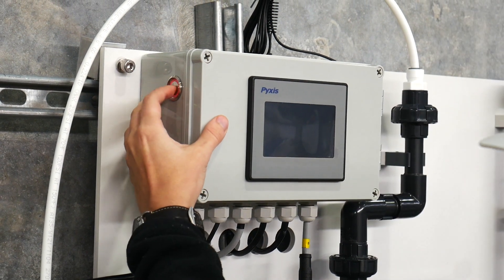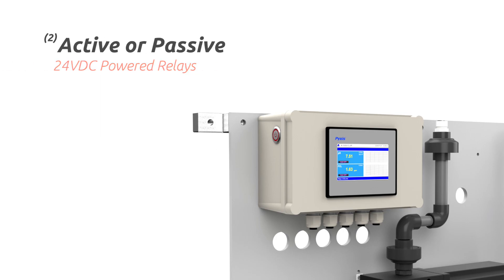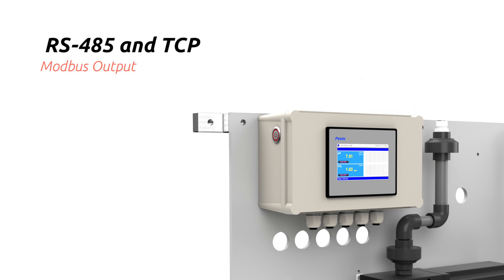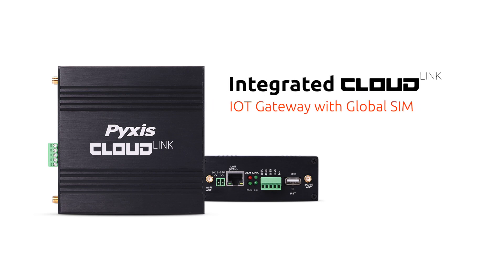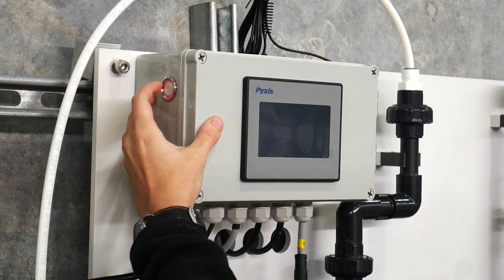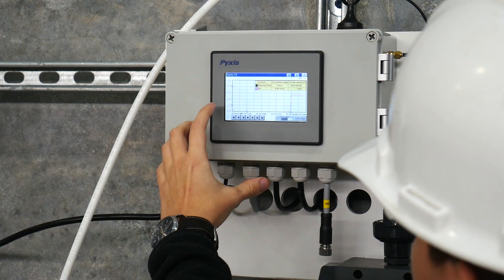The OxyPanel Plus comes with a variety of enhancements versus our standard OxyPanel, including a larger UC80 color capacitive touchscreen HMI display and data logger with two active or passive 24VDC powered relays, three programmable 4 to 20 milliamp output signals, and RS-485 and TCP Modbus output. The display also arrives with an integrated Pyxis CloudLink NB-IoT gateway with a global SIM card for wireless data transmission to your preferred cloud service when activated. The UC80 offers live display of the measured oxidizer with precision of 10 ppb, and also provides the display calibration and data output of the sensor's ORP signal.